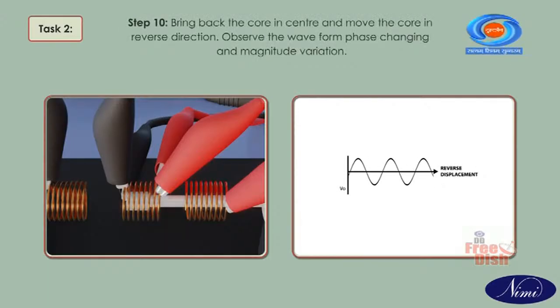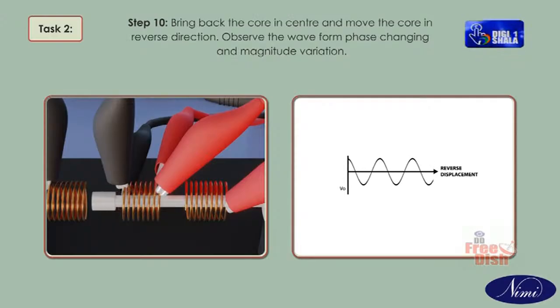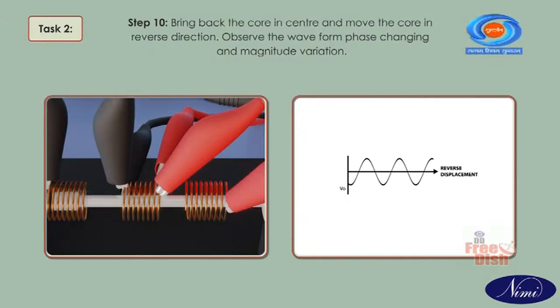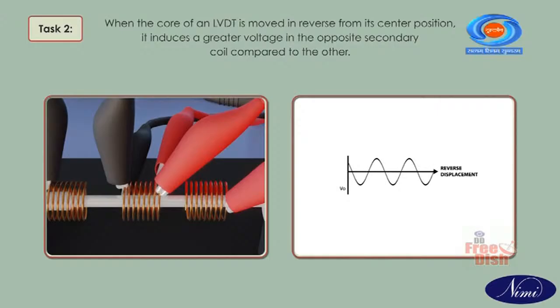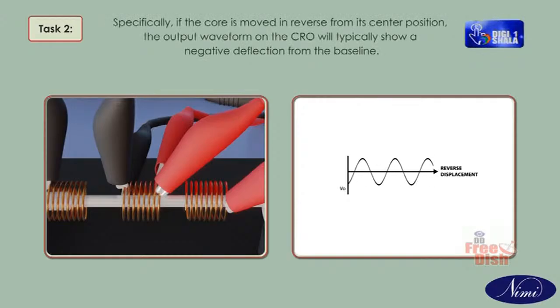Step 10. Bring back the core in center and move the core in reverse direction. Observe the waveform phase changing and magnitude variation. When the core of an LVDT is moved in reverse from its center position, it induces a greater voltage in the opposite secondary coil compared to the other. Specifically, if the core is moved in reverse from its center position, the output waveform on the CRO will typically show a negative deflection from the baseline.